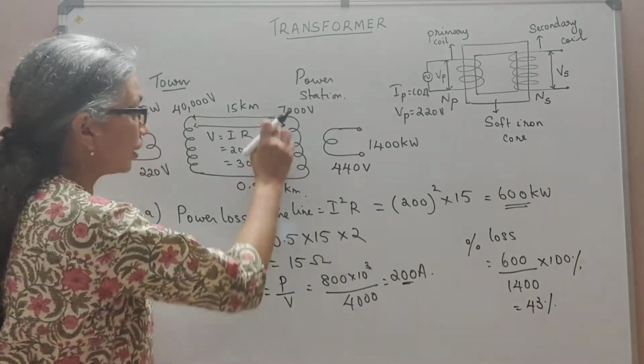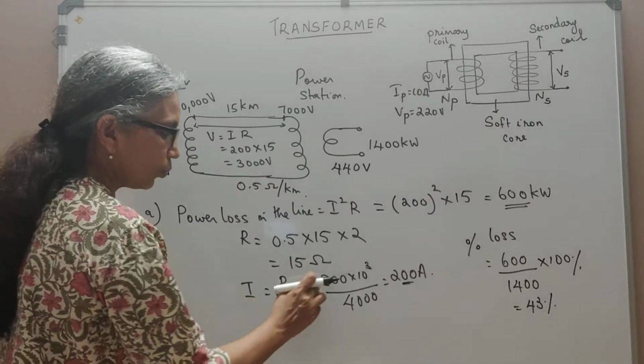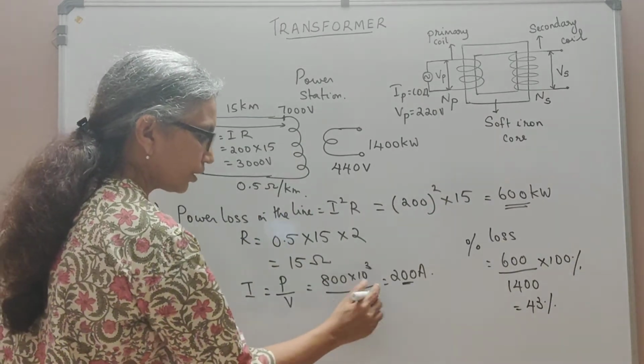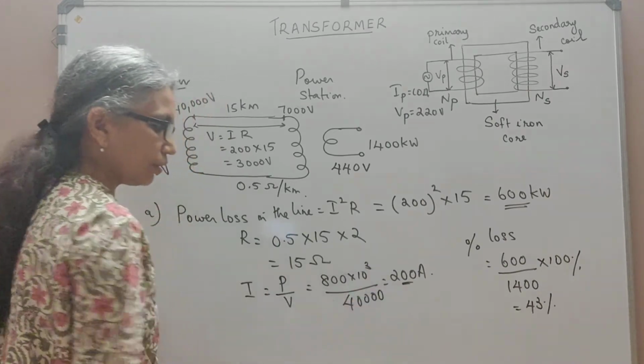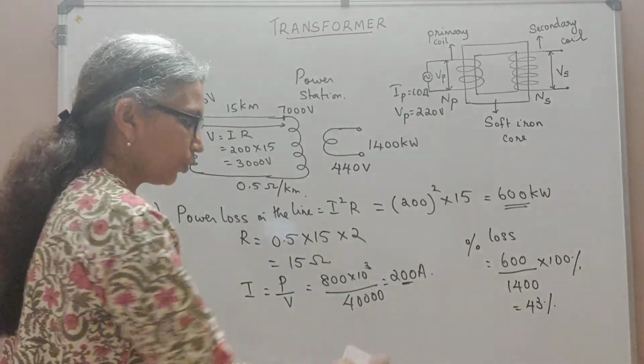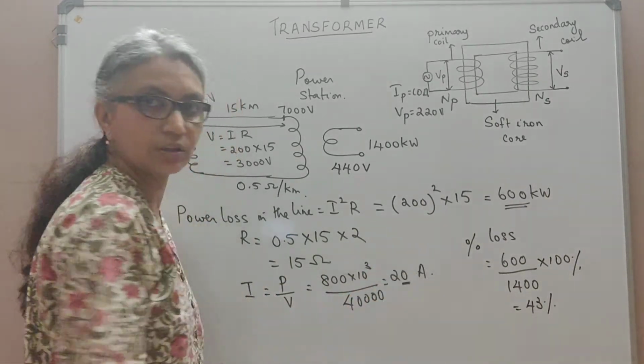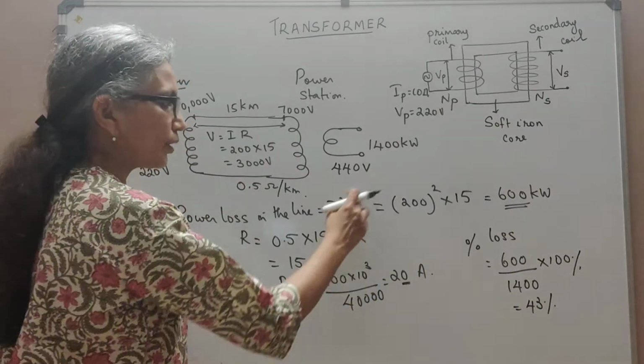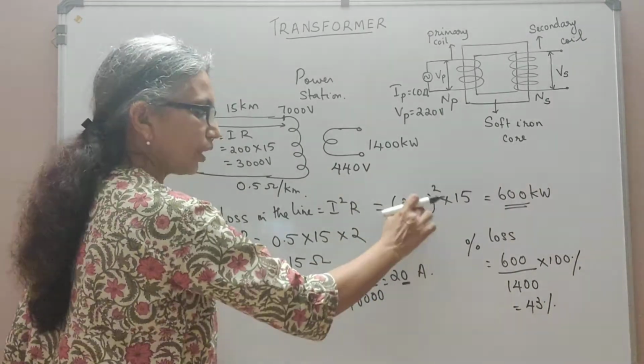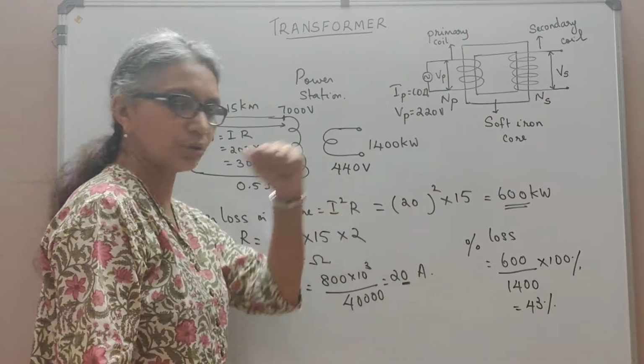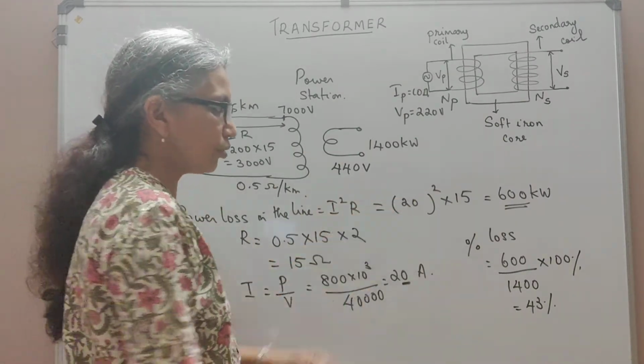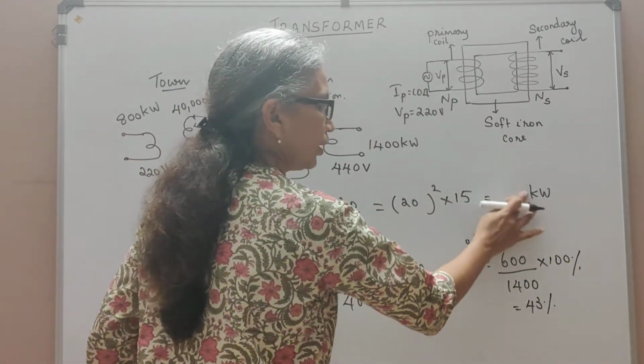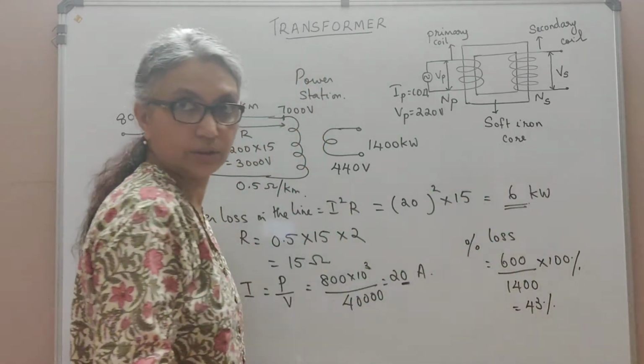But here the current in this line will be 800 kilowatt, but here you will have 40,000, one extra zero, which means your current will reduce to 20 amperes. Which means the loss here will be, we have 20 square into 15, so two zeros gone. That means we only have a loss of 6 kilowatt.